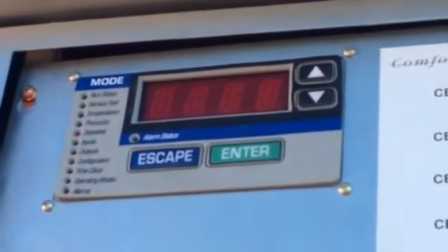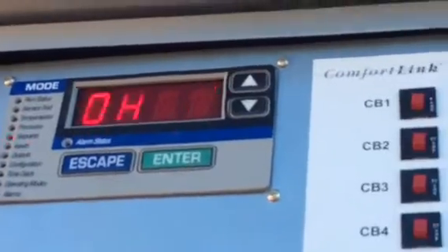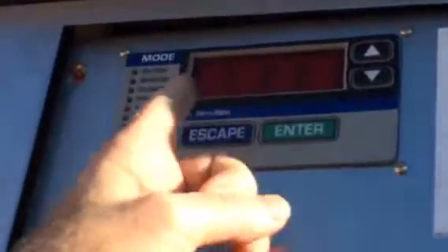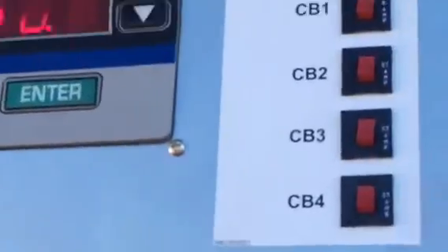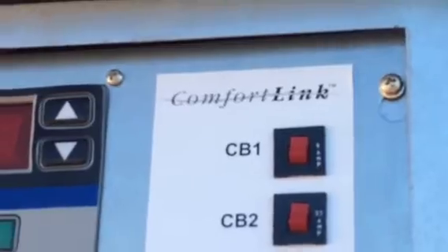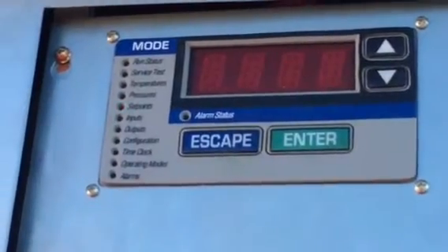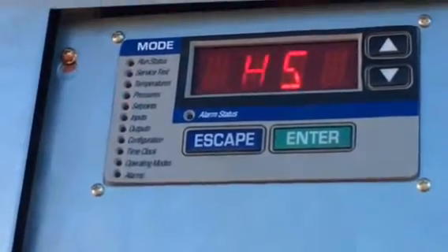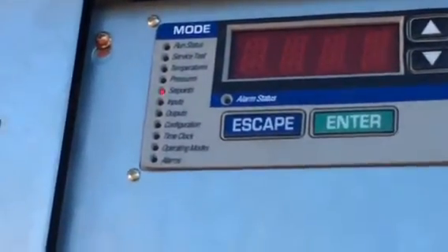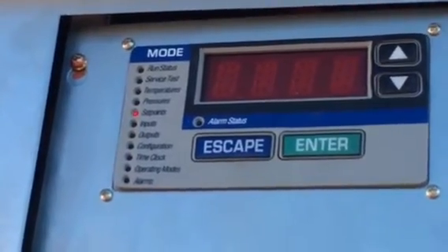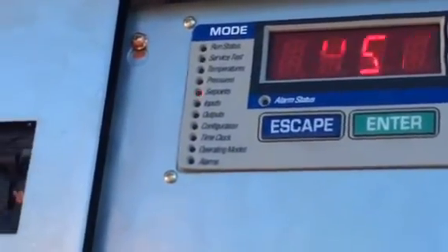So cooling mode, or the ability to start mechanical cooling, is based on a couple of numbers that are added to this occupied heating set point, which is by default 68. So with all default values, cooling is enabled on this one from 72 degrees and up, but now it's going to make its other decisions. Things such as, if I started a compressor and I shot to 45-degree leaving air with only one compressor, I'm going to hold it off before it starts again.